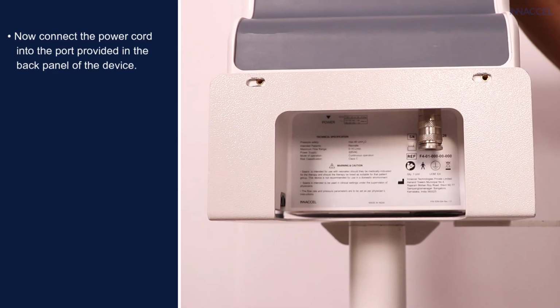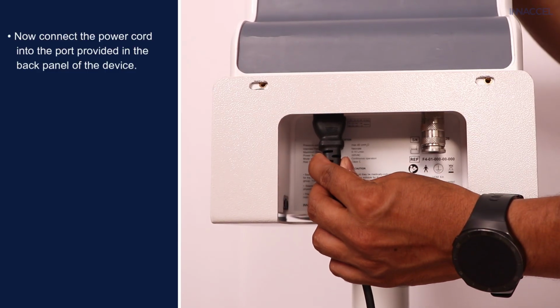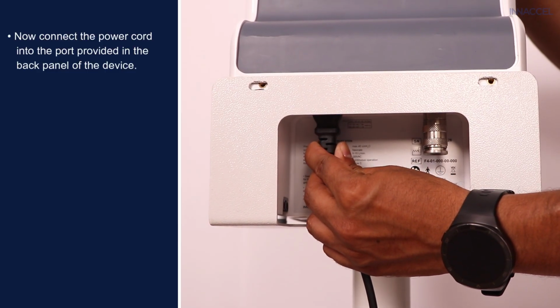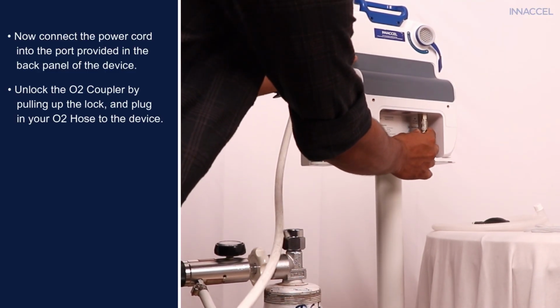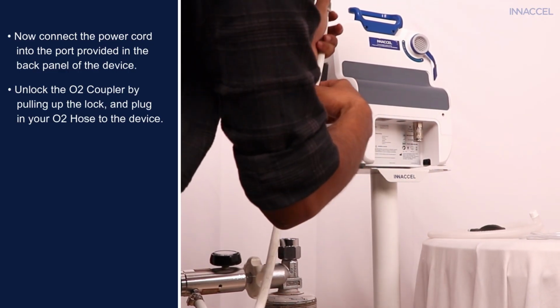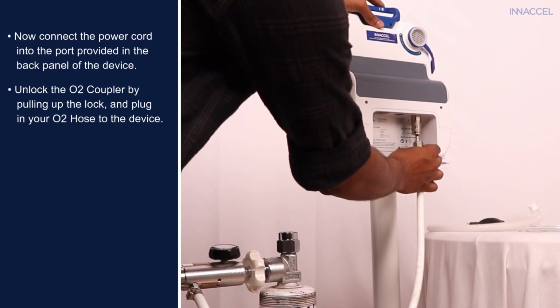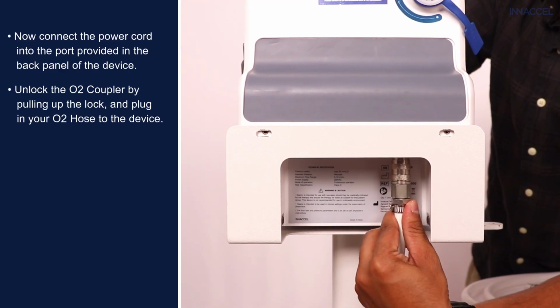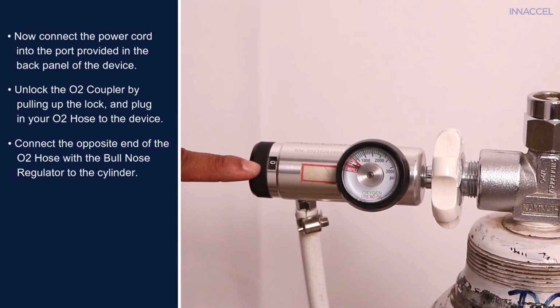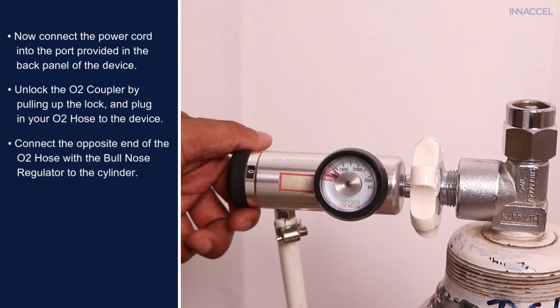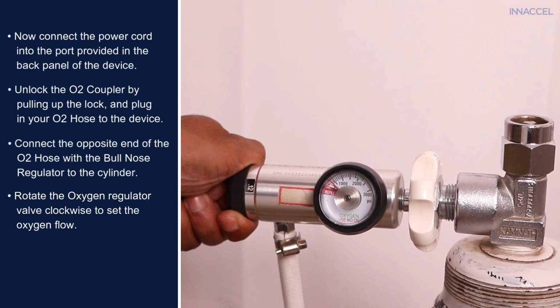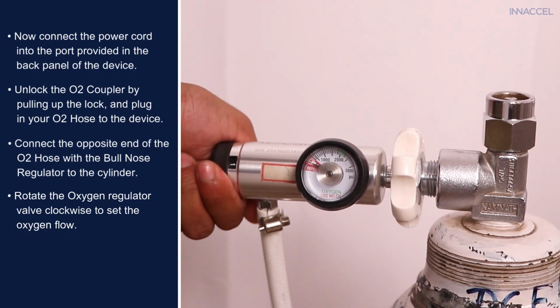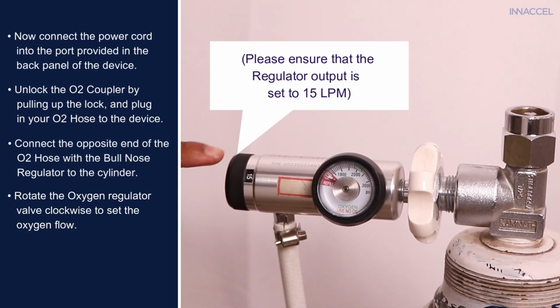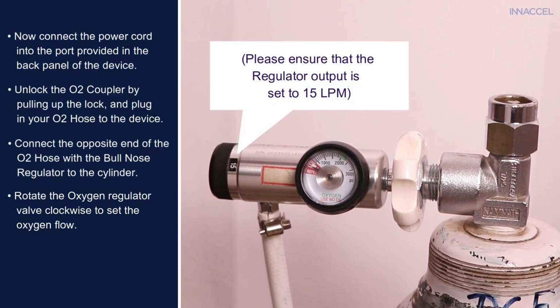Now connect the power cord into the port provided in the back panel of the device. Unlock the oxygen coupler by pulling up the lock and plug in the oxygen hose to the device. Connect the opposite end of the oxygen hose with the bullnose regulator to the cylinder. Rotate the regulator valve clockwise to set the oxygen flow. Ensure the regulator output is set to 15 lpm.